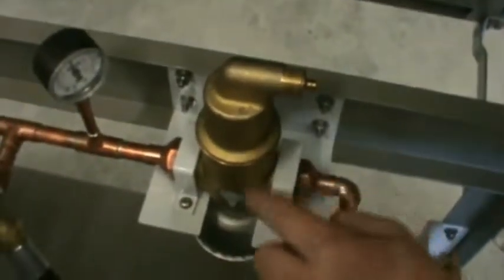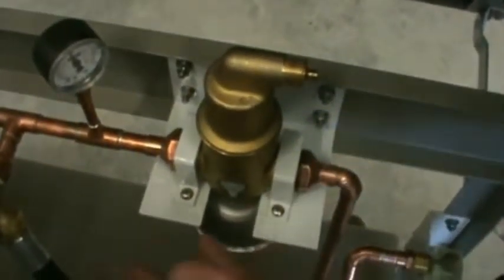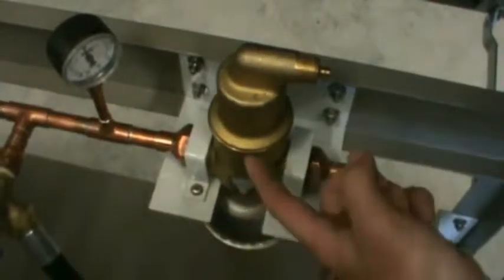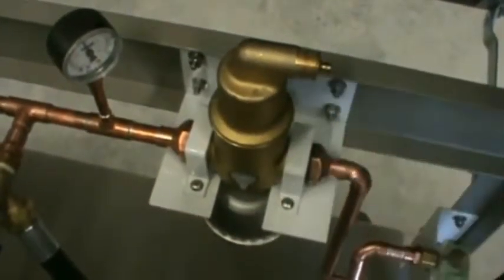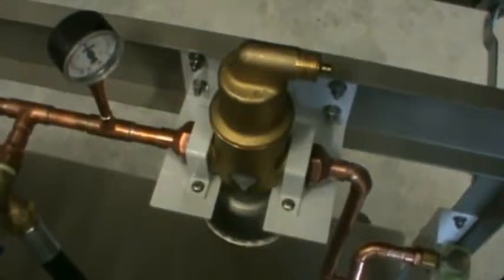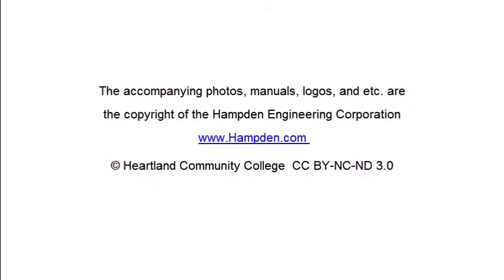We're going to start the commissioning process. The solar thermal collector system is now full. It's got the fluid. Even with these small micro bubbles, we're going to live with that, and the reason why is the spiral vent, which is this vent right here, will eliminate that. Inside there's a small spiral-based system that will collect any air bubbles and allow it to escape and purge up top. And then on the top of the solar collector system there will be a small coin vent.